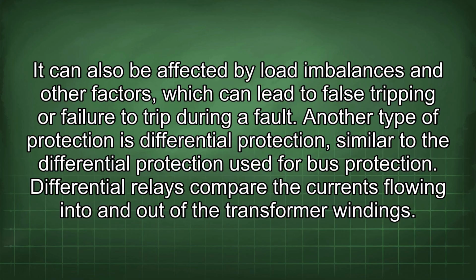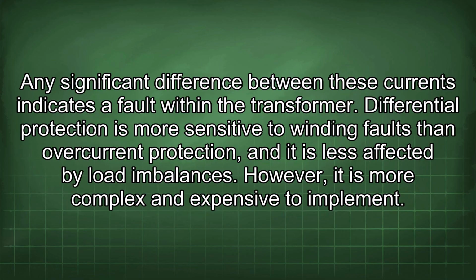Another type of protection is differential protection, similar to the differential protection used for bus protection. Differential relays compare the currents flowing into and out of the transformer windings. Any significant difference between these currents indicates a fault within the transformer. Differential protection is more sensitive to winding faults than overcurrent protection, and it is less affected by load imbalances. However, it is more complex and expensive to implement.